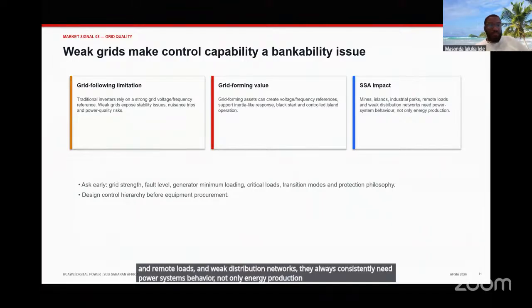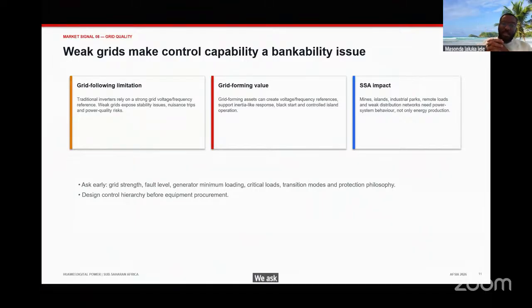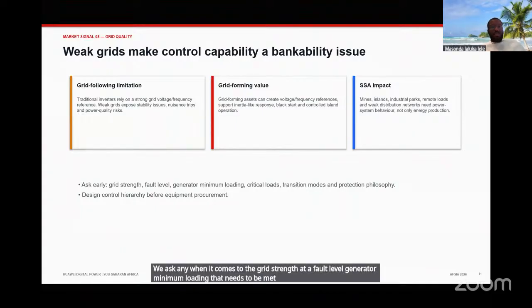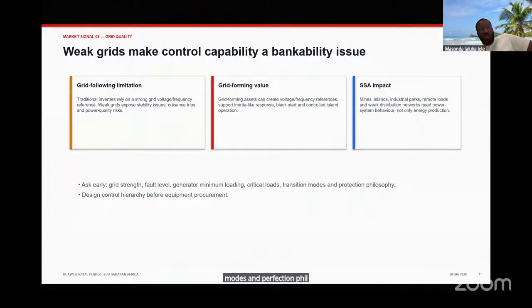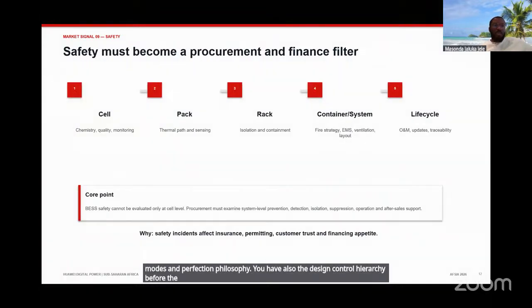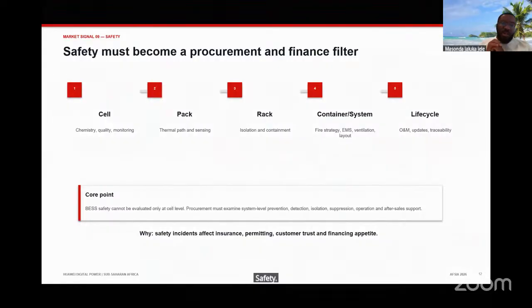We ask, when it comes to grid strength, about the fault level, generator minimum loading that needs to be met, the critical loads, transition modes, and protection philosophy. You also have the design control hierarchy before the equipment procurement. Safety, which is one of our key selling points, must become a procurement and a finance filter.